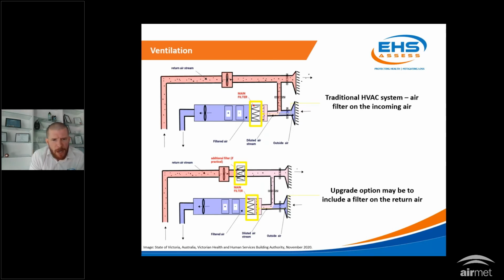Here's a diagram of a typical HVAC system. On the bottom right-hand side is the outside air. Essentially, there's an air inlet where air comes in, and early on in the system there's a filter. The filters generally installed at that point I like to refer to as bird catchers - essentially a mesh or bag filter. Their purpose isn't to capture really small particles, but to capture much larger dust particles, birds, insects, whatever it may be - not to be mistaken as something capable of filtering out a virus. This incoming air is then conditioned, heated, cooled, moisture removed, and ultimately moved around the building.